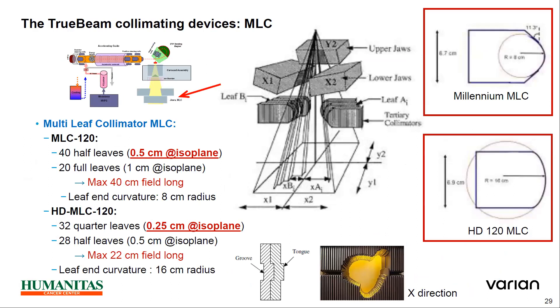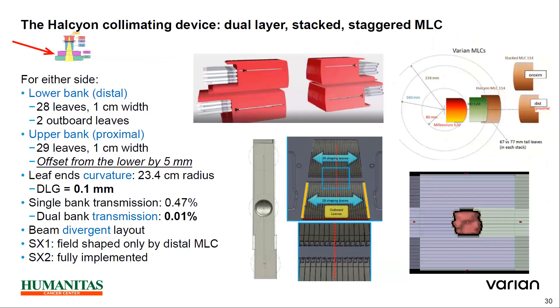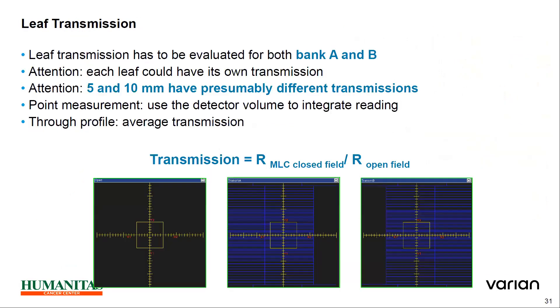For the TrueBeam collimation device, we have MLC 120 or HD-MLC 120. They both have a different leaf radius and curvature, and one needs to know this. Halcyon has a different system; I'm not going to talk much about Halcyon right now. Leaf transmission has to be evaluated for both bank A and B — each leaf could have its own transmission, so 5 mm to 10 mm leaves presumably have a different transmission.